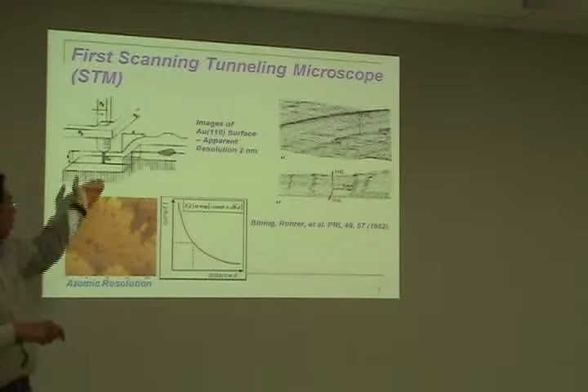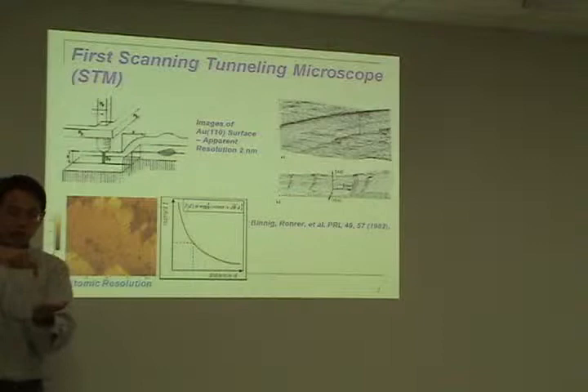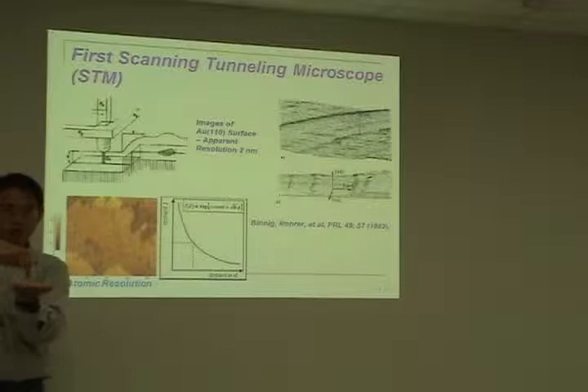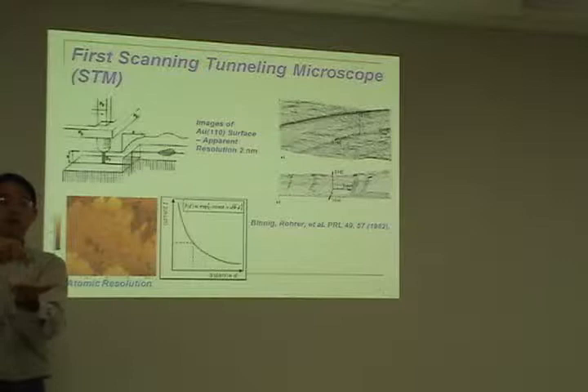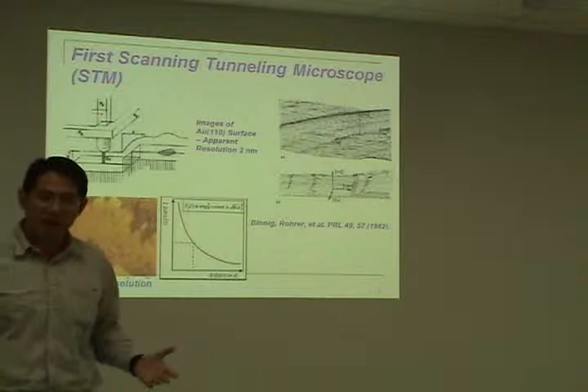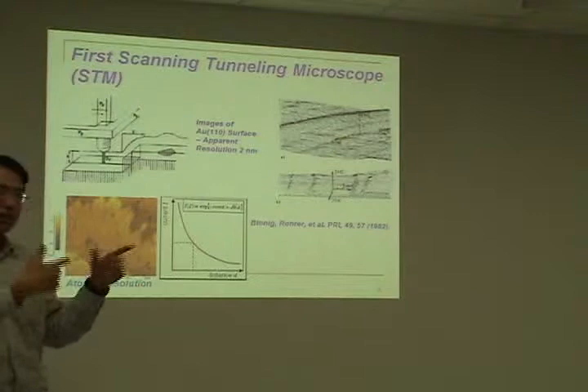The way STM works is it approaches a metallic tip on a metallic sample. It's very close but not in contact — separated by a few angstroms. At that distance, electrons will tunnel through from the tip to the sample or from the sample to the tip. This benefits from quantum mechanics: there is a tunneling probability that is prohibited in classical mechanics but possible in quantum mechanics. So basically this tool collects the tunneling current during scanning of the surface.